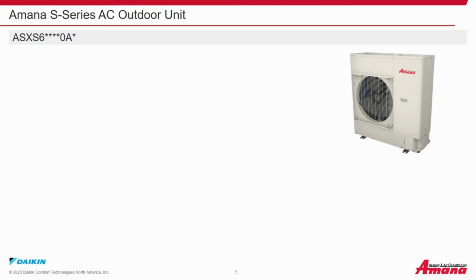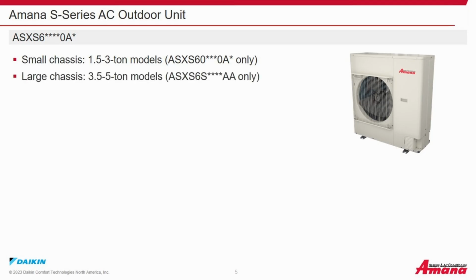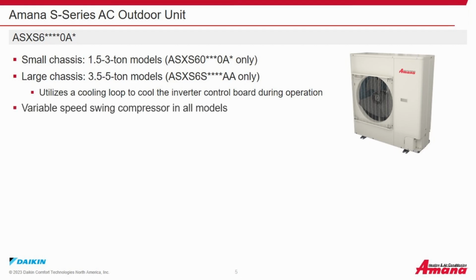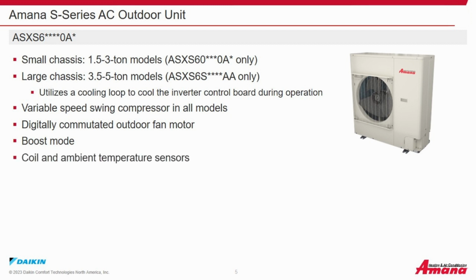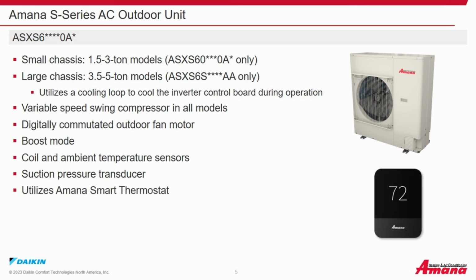The Amana S Series cooling only outdoor unit. The ASXS60A. Small chassis, 1.5 to 3 ton, which is the ASXS6018 through 36. The large chassis, 3.5 to 5 tons, the ASXS6S42 through 60, utilizes a DX cooling loop to cool the inverter control board during operation. Variable speed swing compressor in all models. Digitally commutated outdoor fan motor. Boost mode. Coil and ambient temperature sensors. Suction pressure transducer, and it utilizes the Amana Smart Thermostat.